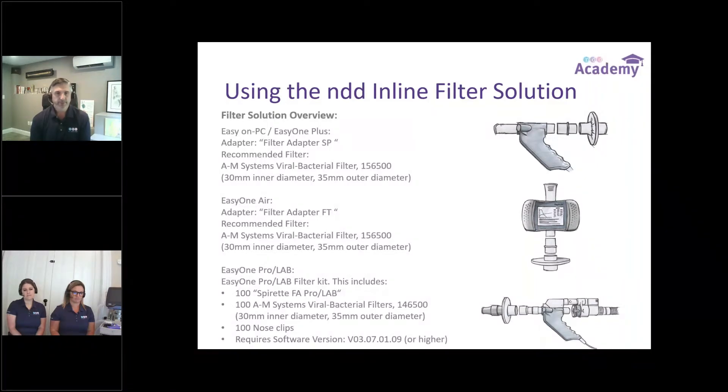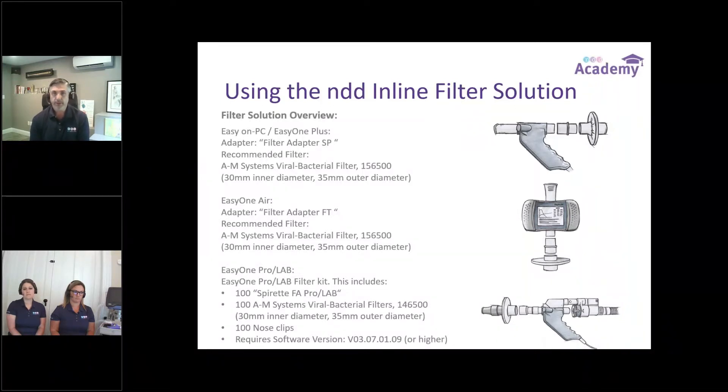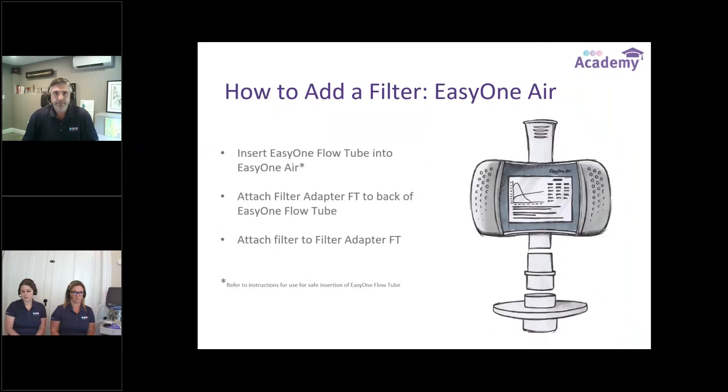On the Pro and ProLab, it's a little bit different. Because of the nature of that device, we had to do something on the front end. We developed a Pro and ProLab kit that includes a Spirette FA and filter adapter combination. Adding the filter and adapter to the front of the Pro provided a little bit of additional dead space and flow linearity, so we made a software update to go with this. It's a combination package — you can get the kit and the software, and the software is free of charge, which will allow you to select that you're using it. The device will then automatically adjust for any changes that could happen.